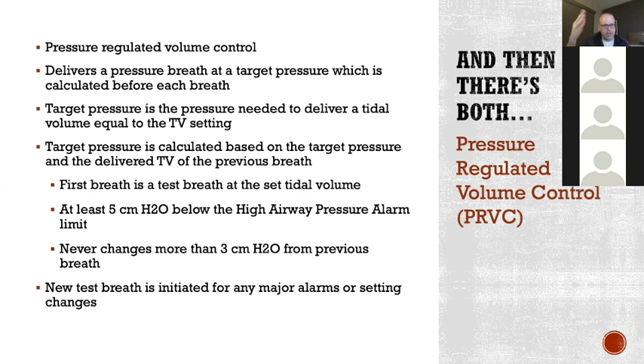If something weird is sensed by the ventilator, meaning there's a big alarm, like it gets back a really low tidal volume or a really big tidal volume, or there's a high pressure alarm on the vent, any alarms that go off, or any changes that you make to the ventilator settings, it's always going to redo that test breath. So it'll redeliver a test breath in volume, see how much pressure it took, and then it will start delivering pressure breaths again.